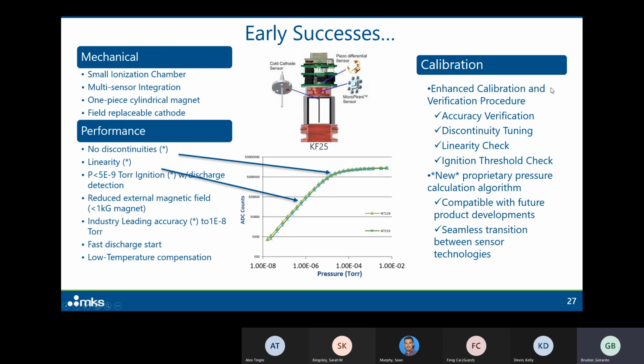In terms of calibration, we developed an enhanced calibration and verification procedure. I don't believe anybody else in the industry even knows how to do this today. So this procedure includes 4 basic steps. First, we do a calibration followed by accuracy verification. Then discontinuity tuning: we make sure that every gauge that ships to a customer is free of discontinuities, which is critical for accuracy. We do a linearity check on every product that we make, and we also do an ignition threshold check on every product that we sell.